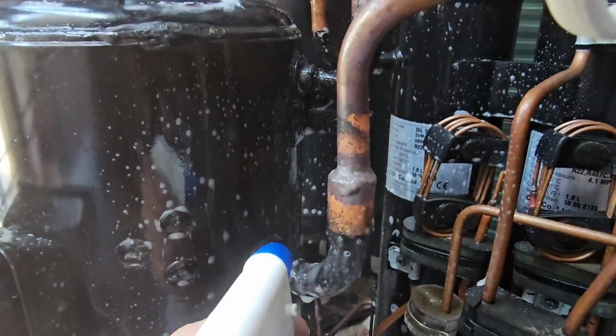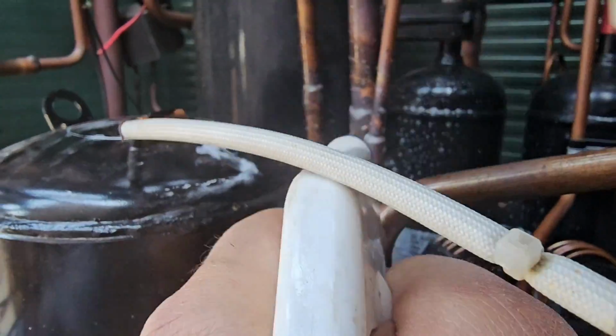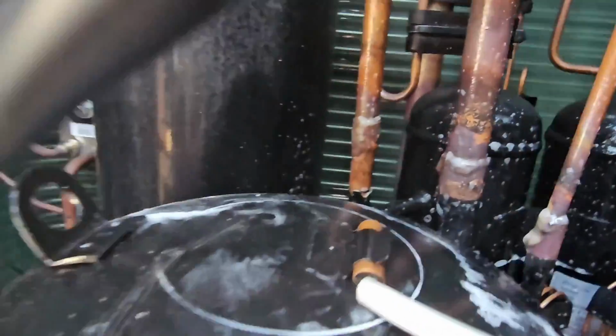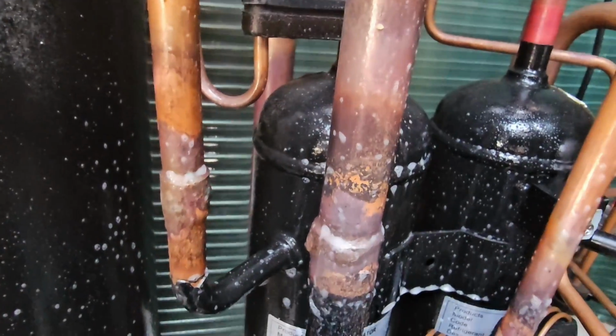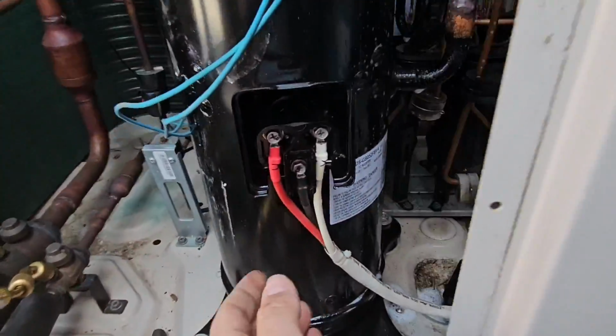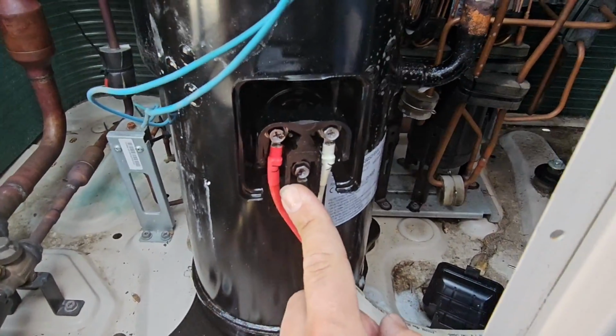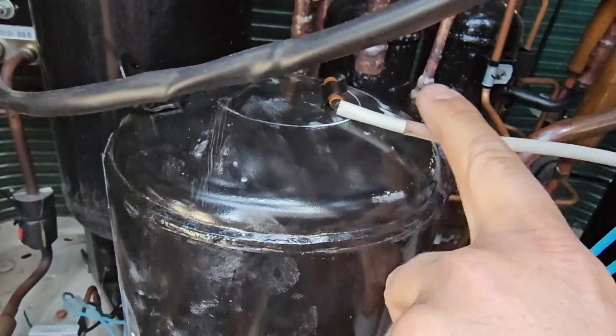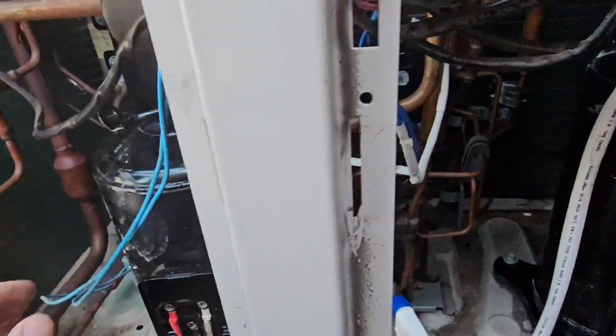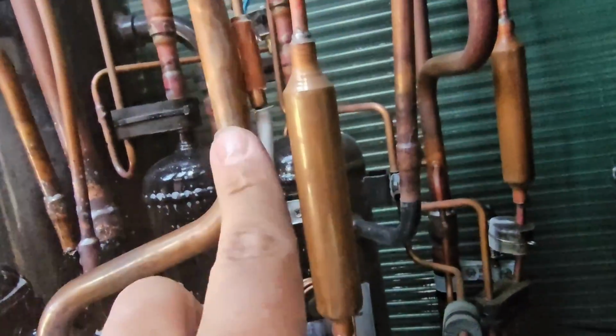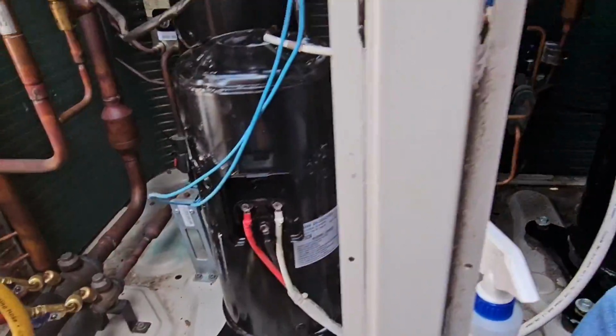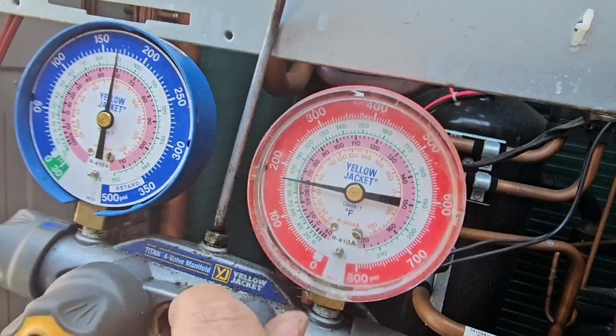Leak testing all the fittings. Make sure I don't have any leaks. I don't think I will, because I made sure of that when I was brazing, but I'm going to make sure I don't have any leaks. And I've already put the wires back on the compressor, put the sensors on top, thermistors, top sensors, and then discharge sensors. I put those back on the discharge pipes. Getting close to being ready to start it back up.